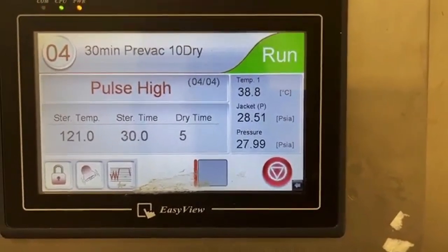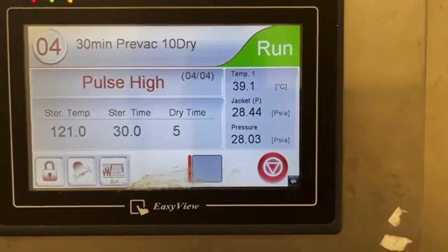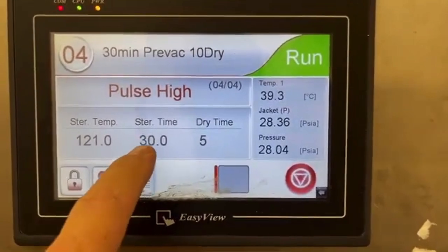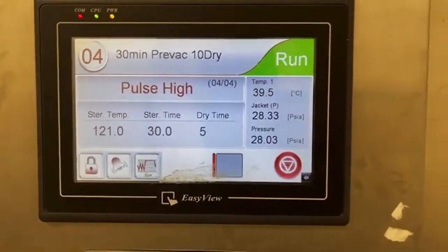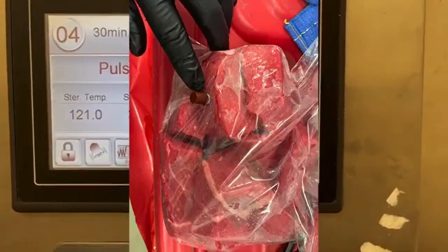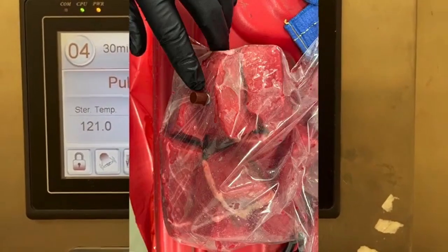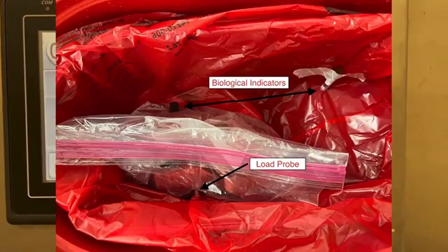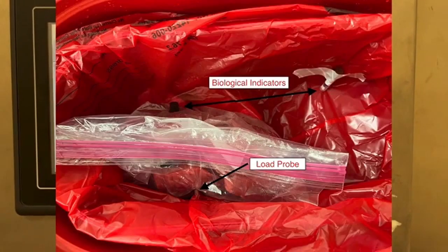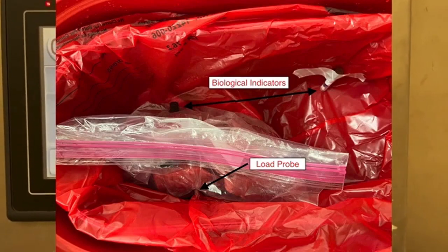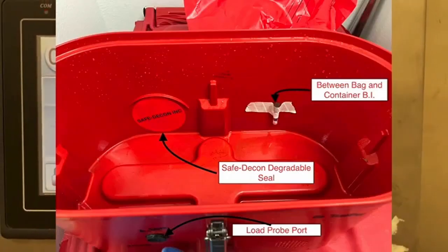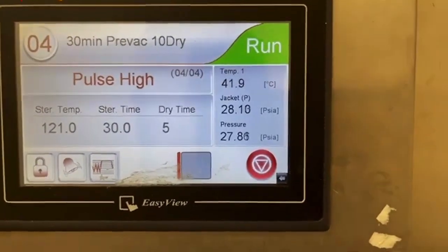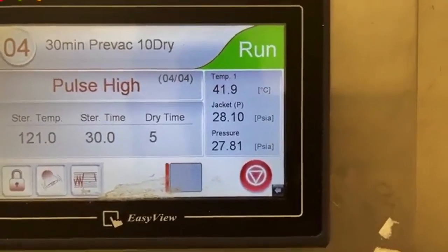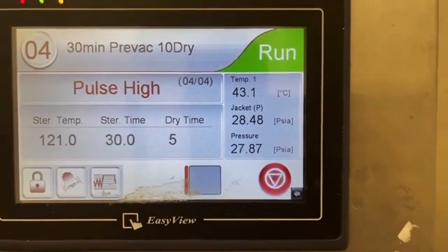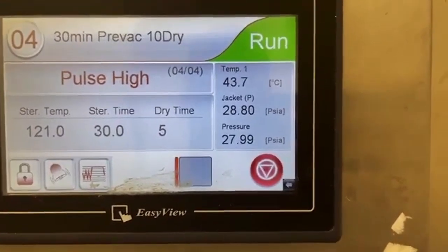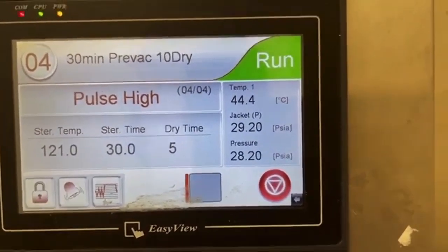And then when it goes over 2, you're going to see. Now I'm running a 30-minute. The last one I ran was a 40-minute. I have a biological indicator in the middle of a 6-ounce piece of meat. Then I have a biological in the well where it collects the liquid. And then I have a biological indicator in between the bag and the container. So as you can see, we're starting to really jump up there right now. So when it gets done with pulse high, we're going to go into heating here shortly, and then it'll continue on to heat up.